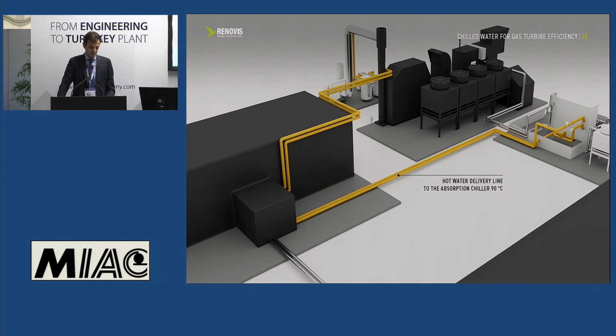Hydraulically, our system is very simple. The hot water at 90 Celsius degrees generated by the heat recovery system I mentioned at the beginning is directed to a distribution substation from which it is diverted, depending on the season, to the heating systems in winter or to the absorption chiller in summer. In this slide, we see exactly the hydraulic pipeline branch that feeds hot water towards the absorption chiller.